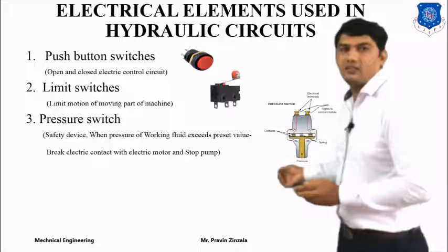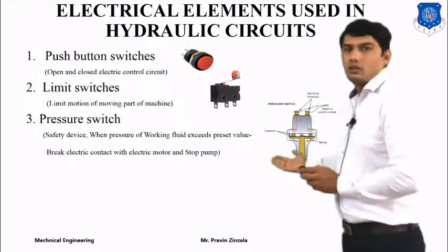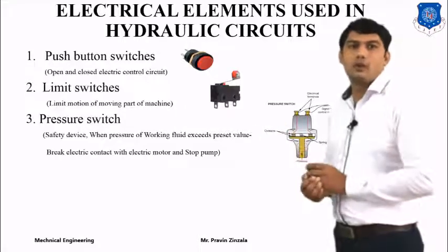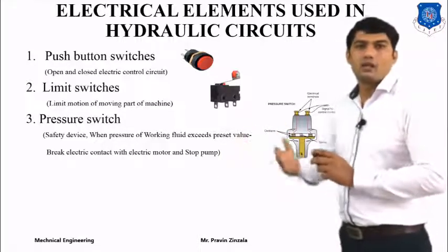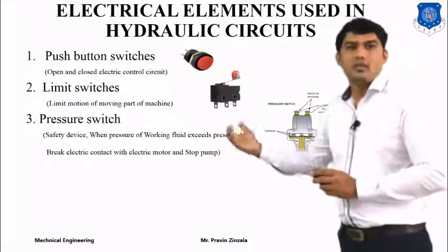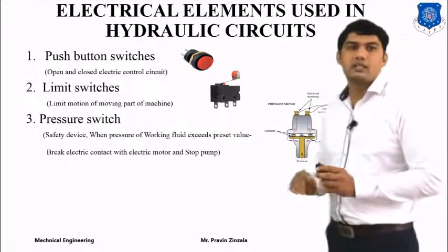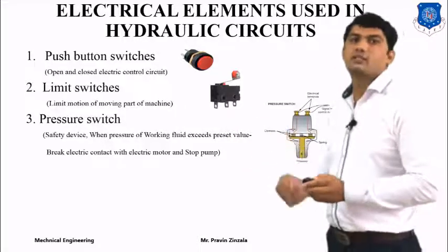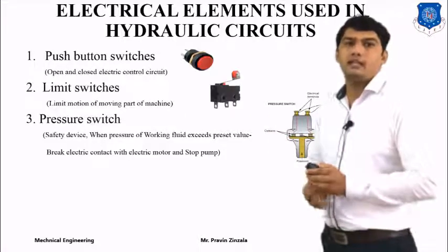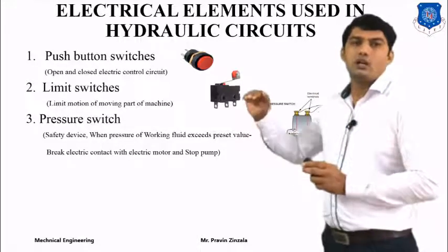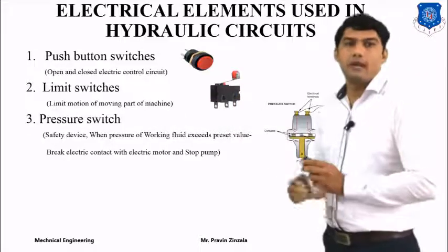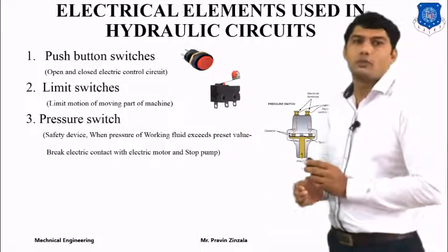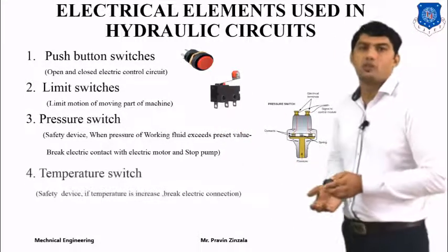If our design pressure is exceeded, the switch will break the contacts of the pump and of different components, and our components will come to a steady position. If the pressure increases beyond our preset value, it will break the contacts of the pump and electrical motor, the motor will stop, so the pump will also stop and our system will come to a steady position.